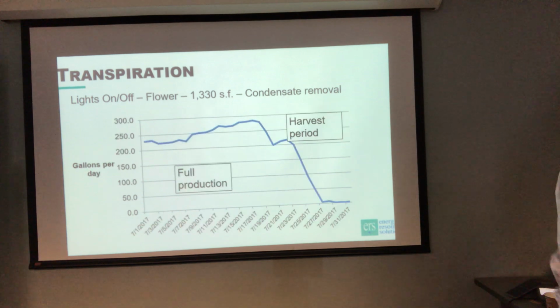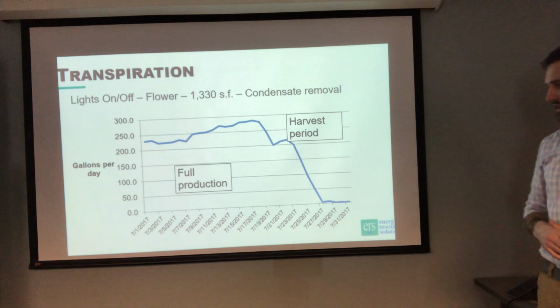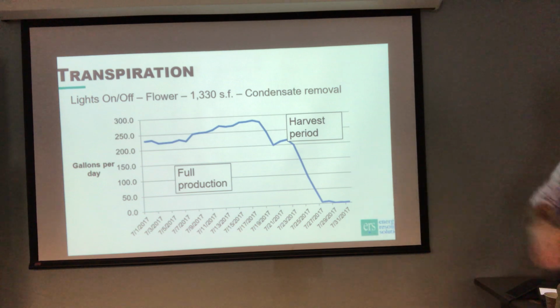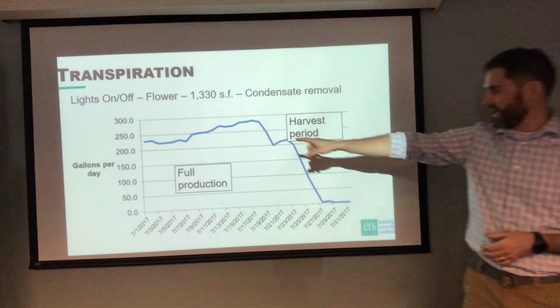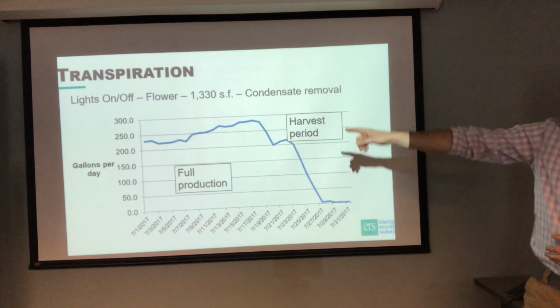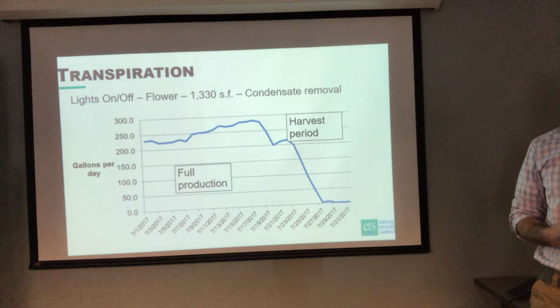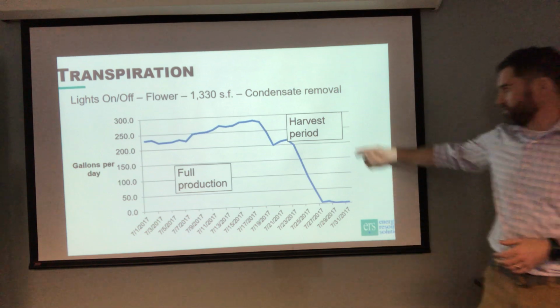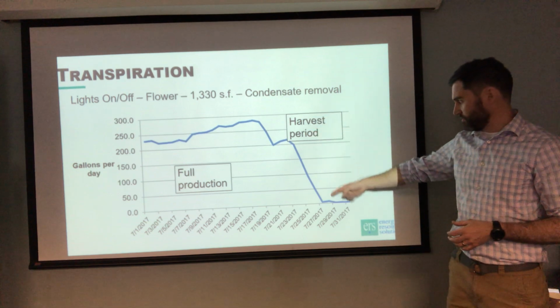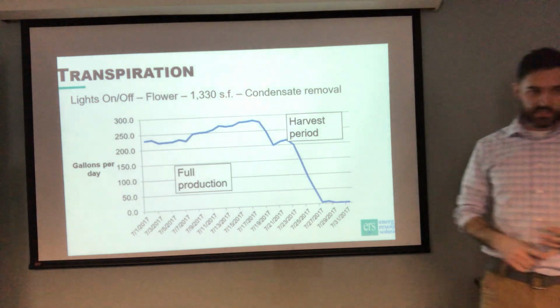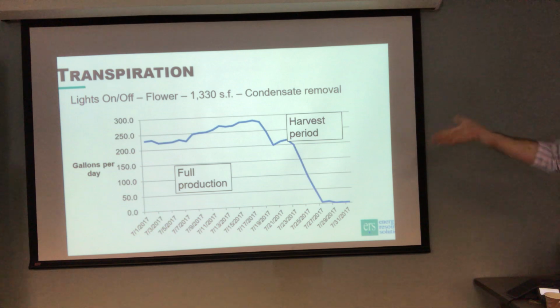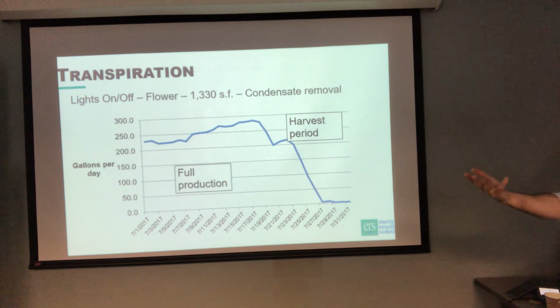So what does that look like a little bit more over a full flower cycle? This is the same facility, and again, this is just the tail end of a flower cycle. 1,300 square foot room, and you can see again, this is now gallons per day, up over 250 gallons per day that we're pulling out of the air of this space. And then, as you can see, once harvest begins, just an absolute precipitous drop-off in the amount of transpiration that's taking place, the amount of condensate that's being removed. That's kind of obvious, like, yeah, you took the plants out, of course, but I just want to drive home the point that the plants are the dominant force in these facilities. Their need for light and the need to remove the moisture that they exhale, those are the dominant forces here.